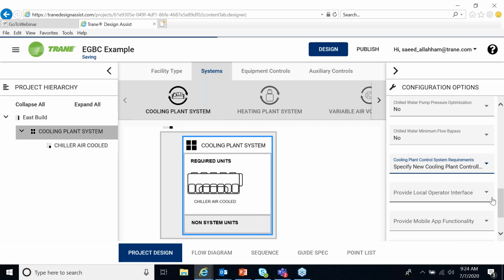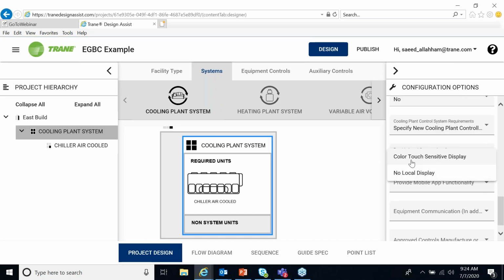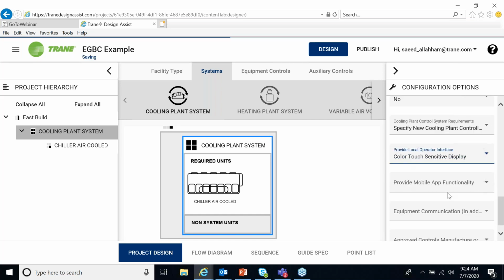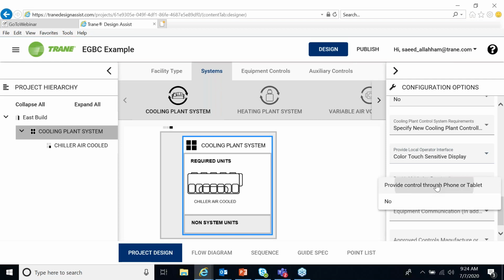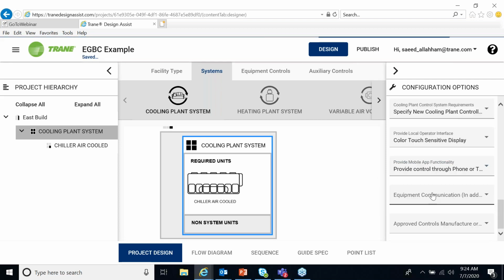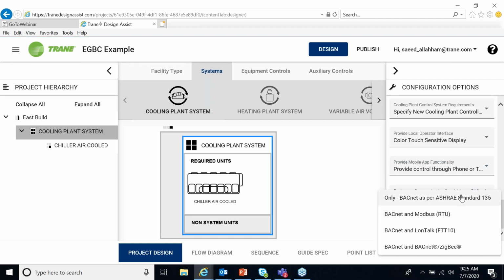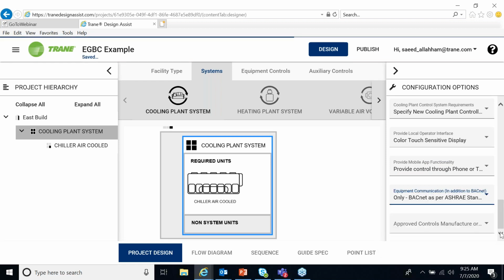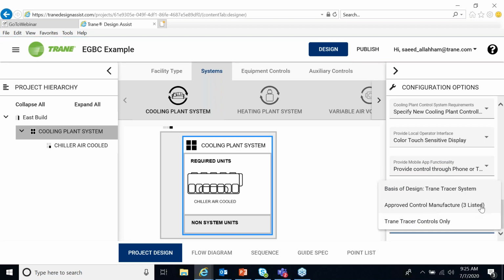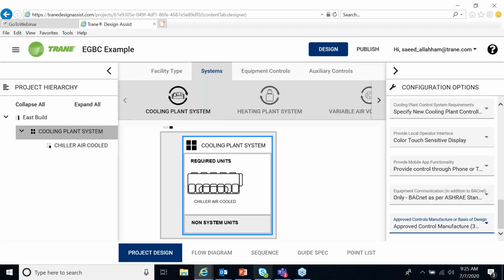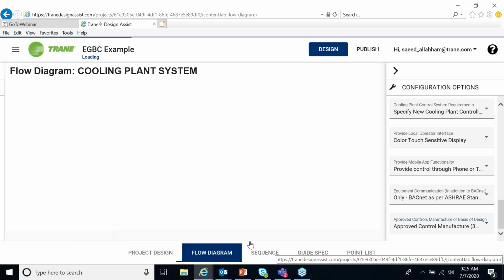Specify new cooling controller. Local operator interface, we want display, we want mobile app, we can choose no. Equipment communication, BACnet, or any other communication. And here you can say 3 approved manufacturers, or you can select 1 manufacturer. So we finished the configuration for the cooling plant system. We can go to the flow diagram.